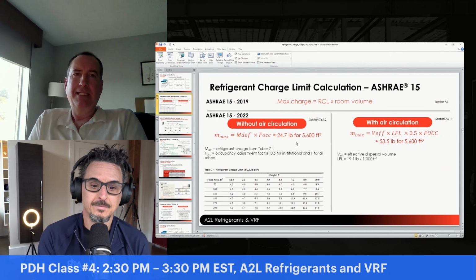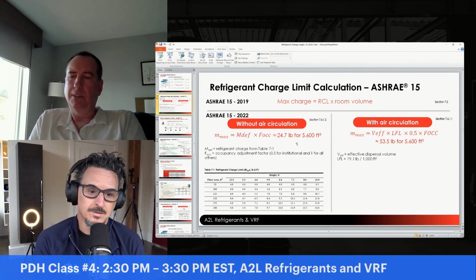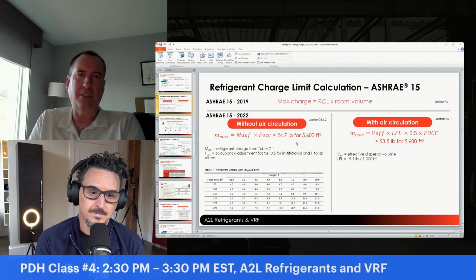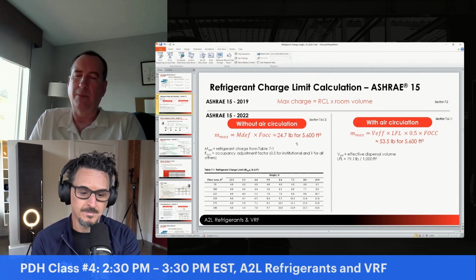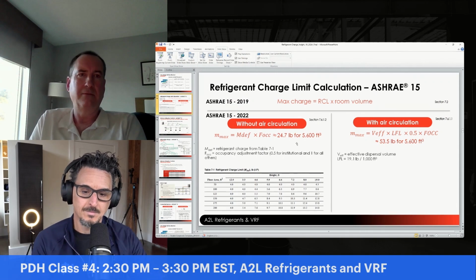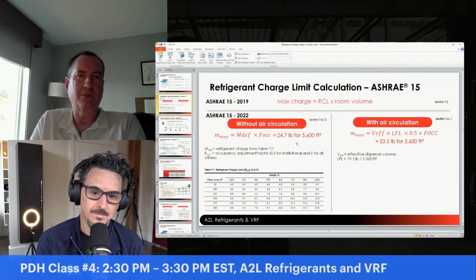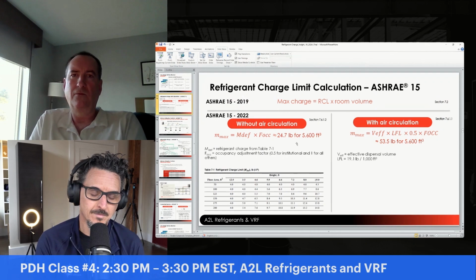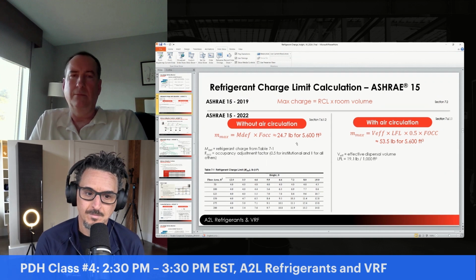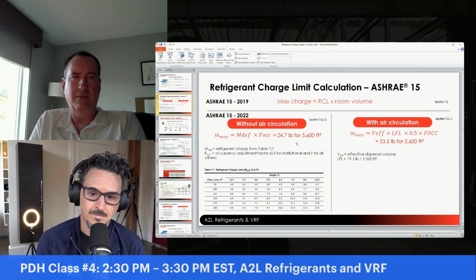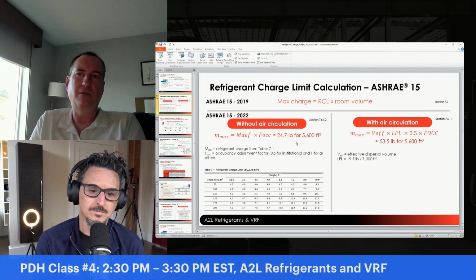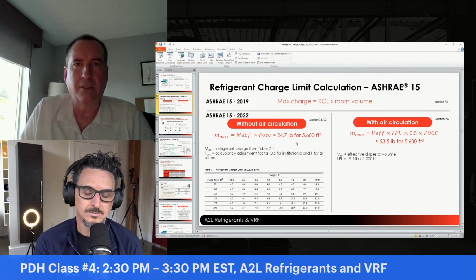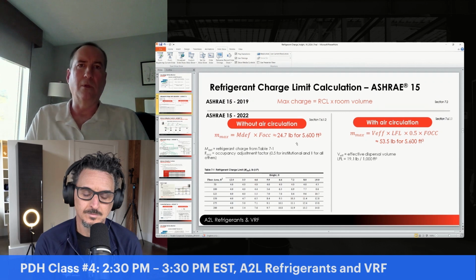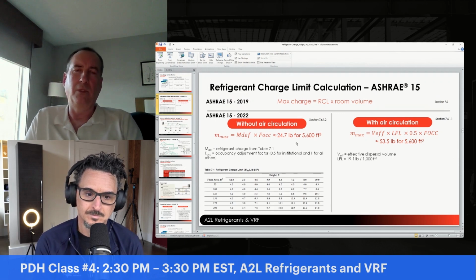Yeah. Now, if you do have air circulation, and that can be continuous or initiated by refrigerant detection sensors or whatever, your max charge then is the LFL times 0.5 times the room volume. So for that same size, same volume of room, you can have 53 and a half pounds of refrigerant. So this shows you how these concepts of circulation actually give you a lot more flexibility than we had before.